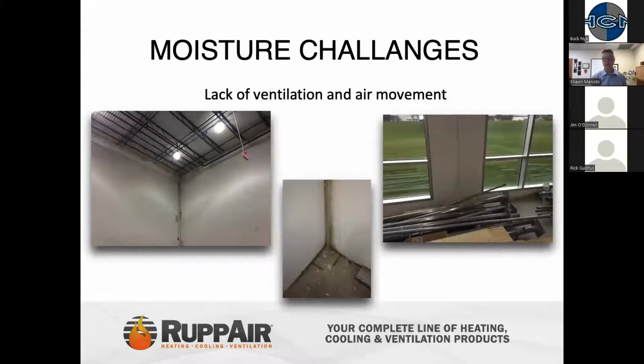So one big challenge we see specifically in these speculative style buildings is moisture issues. This is just some snapshots of a project. I think this project was in Chicago, if I remember right. But this shows why lack of ventilation and air movement in that spec phase is so critical. We've seen this multiple times where now you're into mold remediation. You're basically paying an expense that did not have to be paid. So you can see the mold in the corners. Any place you have a conductive surface, you're hitting that dew point level, you're basically conducting and creating mold.